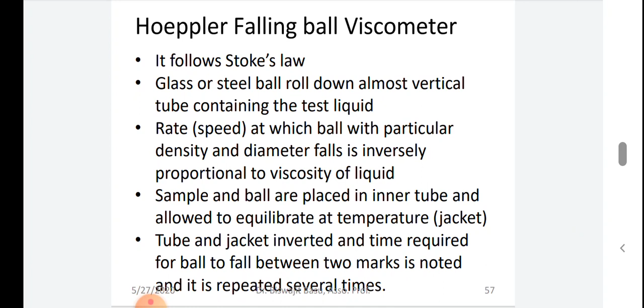Sample and ball are placed in the inner tube and allowed to equilibrate at temperature. Tube and jacket are inverted, and the time required for the ball to fall between two marks is noted down, and it is repeated several times. And viscosity is calculated by using this formula: eta is equal to T (SB minus SF) into B. T means time interval in seconds, SB is the specific gravity of the ball, SF is the specific gravity of the fluid, and B is the constant for a particular ball which is supplied by the instrument manufacturer.